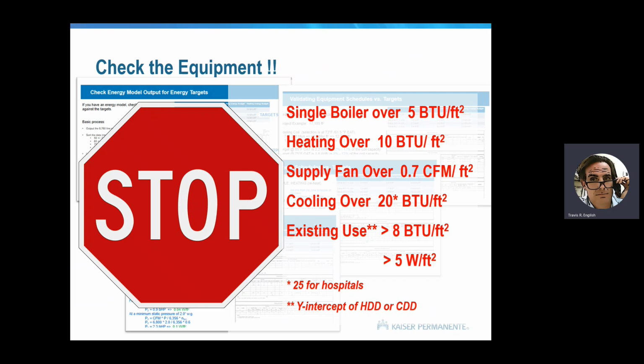We do have to check the equipment to make sure that it can actually achieve a lot of the turndowns that are necessary in the system and that it's actually sized appropriately for the system, right? So if you're thinking about installing a boiler that's more than 5 BTU per square foot, that means you're never going to achieve the turndown that you need. So stop right there. We need to talk about that.